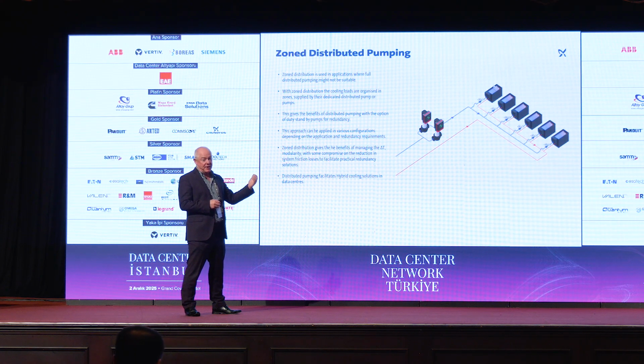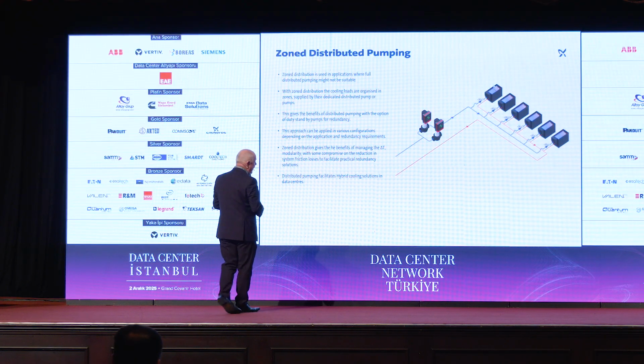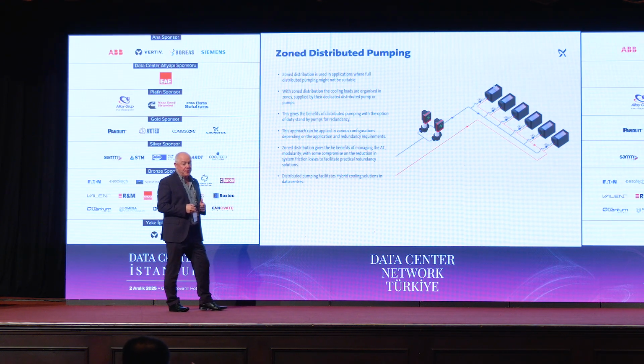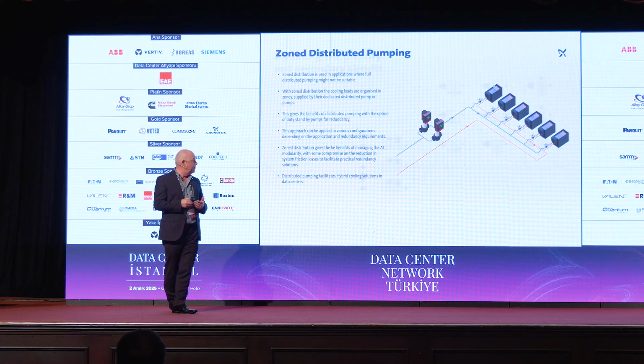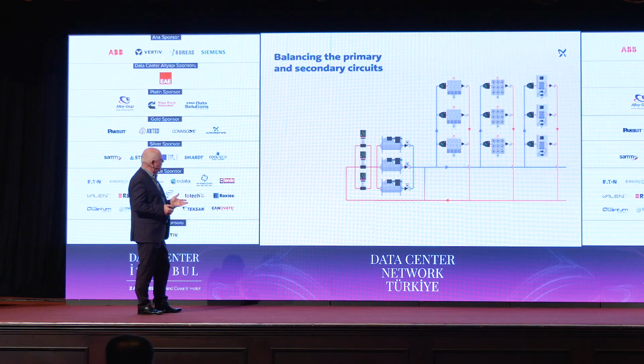At that stage, we're using valves again, but we're not using as many valves in the system, so we're not getting the full energy savings we get with a complete distributed pumping system, but it's a halfway point for people who can't or don't want to use a full distributed pumping system. And I'll go through how it works and how we balance the systems now.